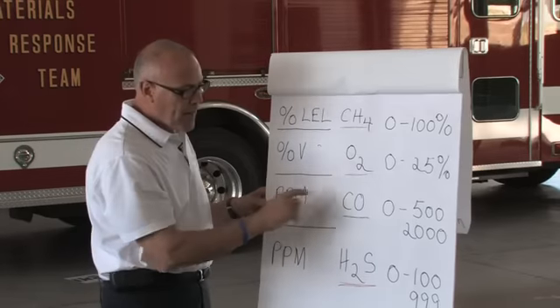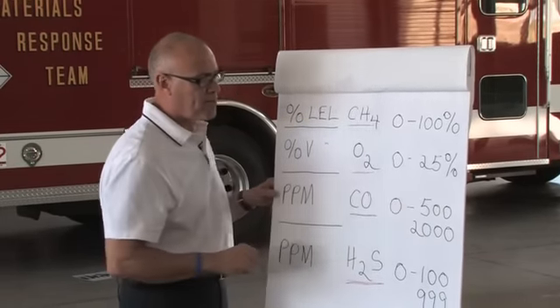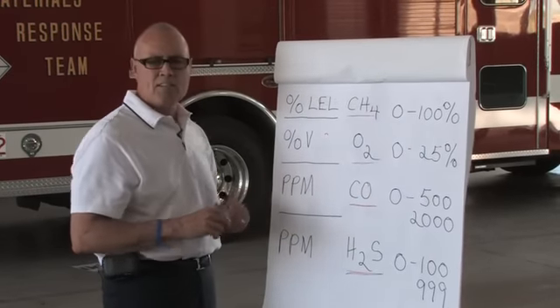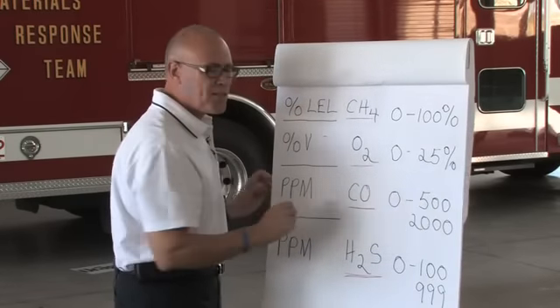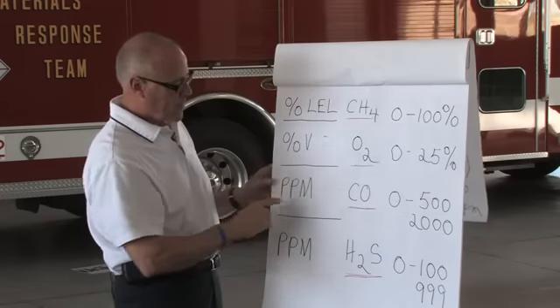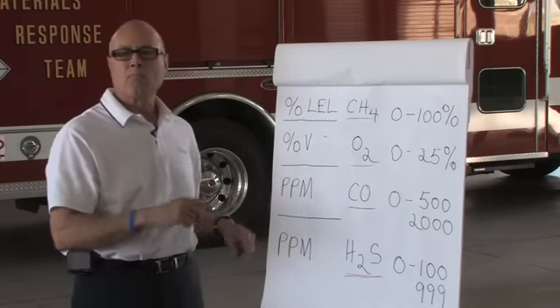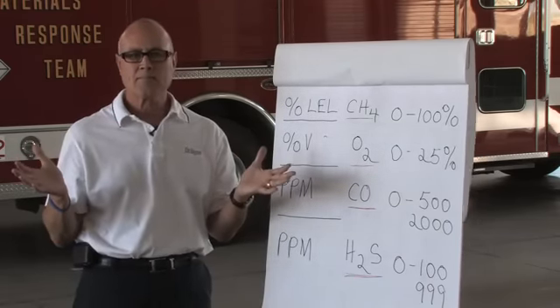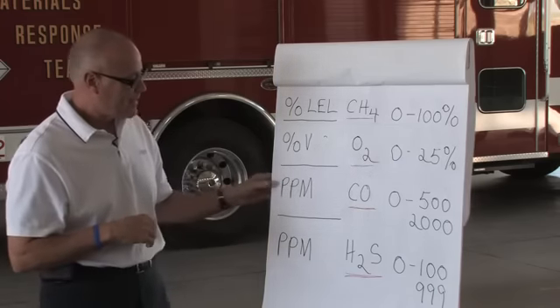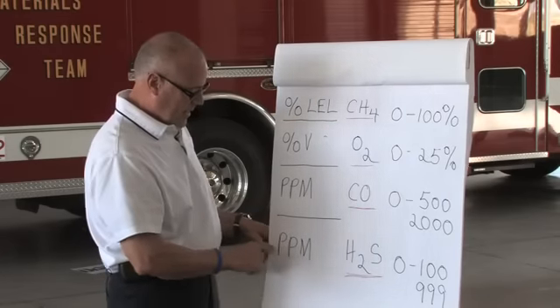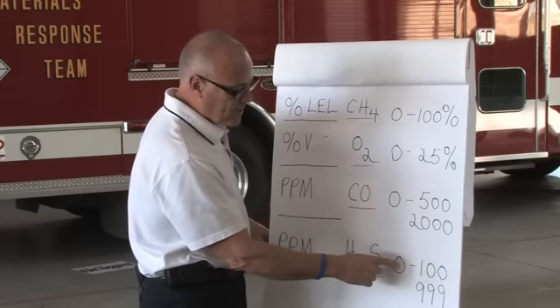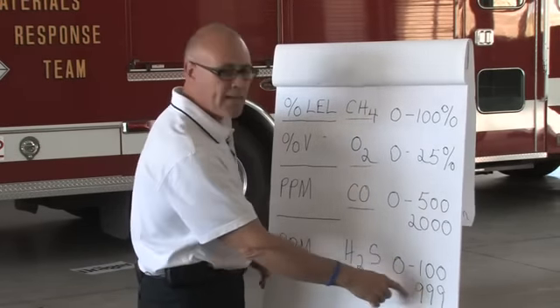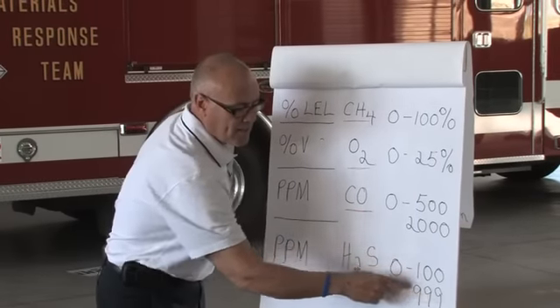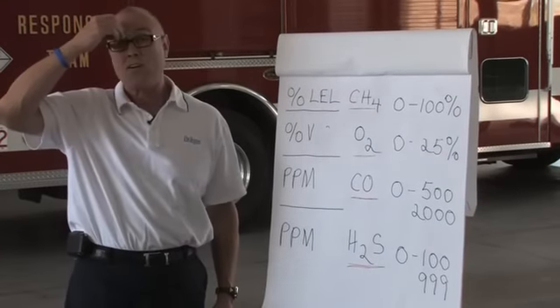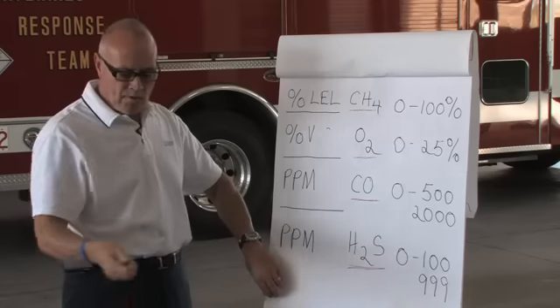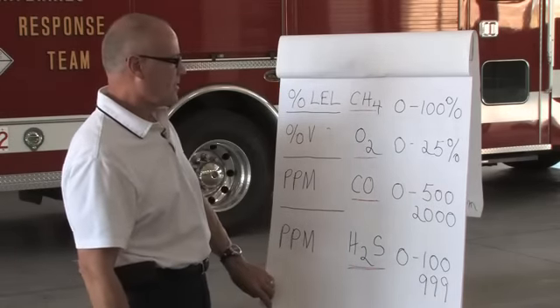Carbon monoxide. I put 2 numbers here, meaning 2 scales, 0 to 500 parts per million, 0 to 2,000 parts per million. Draeger makes different sensors that can go lower concentrations full scale or higher concentrations full scale. We're monitoring in the parts per million range. 1 part per million is 1 part of gas per 1 million parts of air. So it's a very minute amount of gas. Hydrogen sulfide, again, we're monitoring in the parts per million range. Generally, your scales are 0 to 100 in your multi-gas meters, but you can go up to 999 ppm if you'd like. The oil refineries like to have this in the oil production fields because they're dealing with very high concentrations of H2S when they're monitoring at the well. So that's why we have different scales.